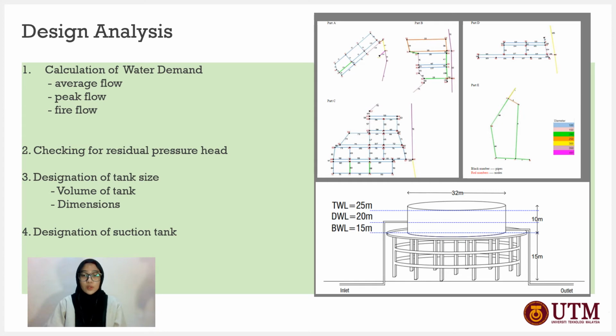Then, fire flow. To determine fire flow, the demand for each node was determined to locate a suitable node for hydrant flow. Node 30 was chosen for hydrant flow as the elevation is high from the tank. The value of hydrant flow added was 22.73 liter per second.